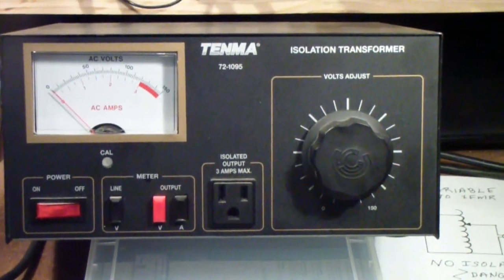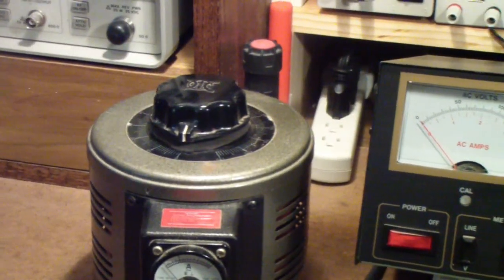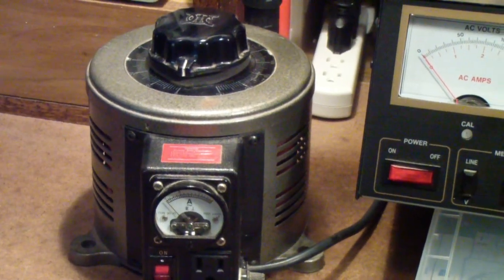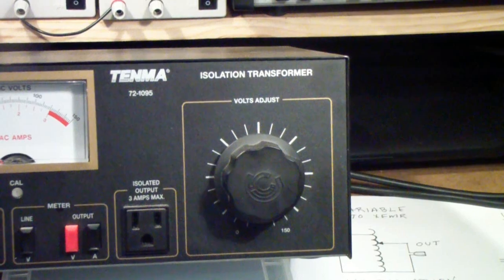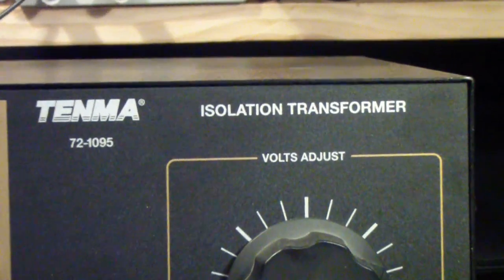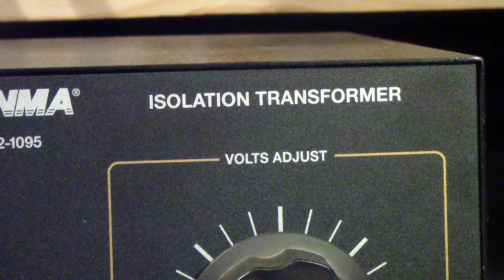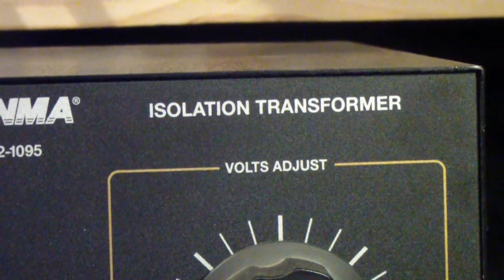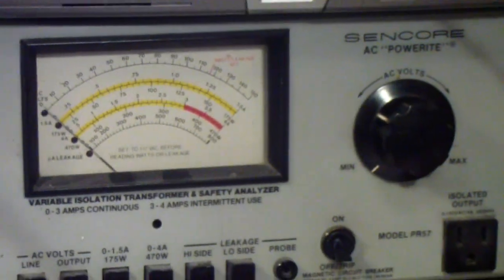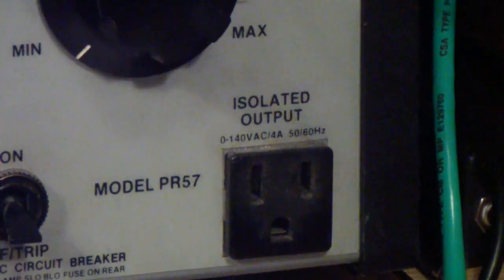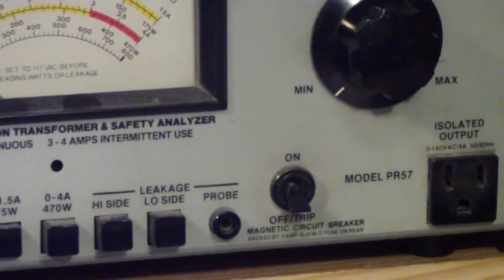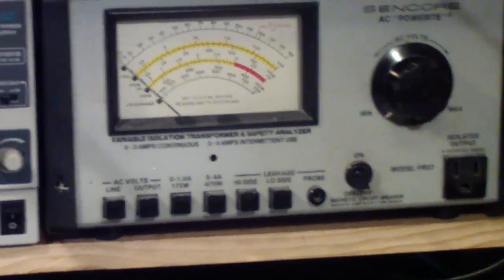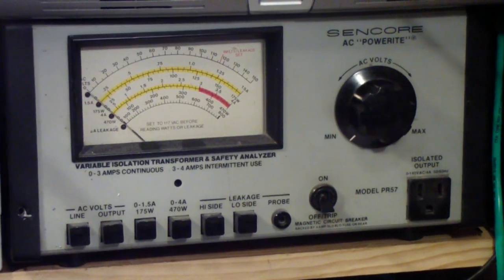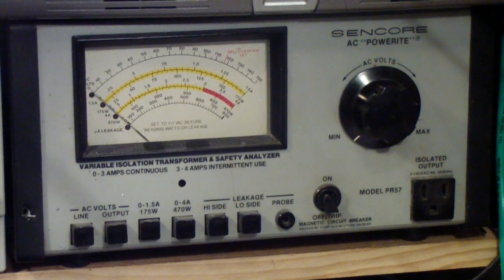The unit you see here is made by, or at least sold by, the same company that sells that auto transformer that is not isolated, but this one is isolated. Notice it says that very clearly right up here. In general, if a unit does have isolation, it'll say so on the unit. This is a unit I used to use, and it does provide isolation. The unit I'm currently using - not because there's anything wrong with that one, but because it provides one additional feature - is the Sencore PR57, which is also isolated. Notice it says that right there. So if you're using something that does not have the word isolation on it, or you're just unsure what you have, do not trust it to be an isolation transformer.